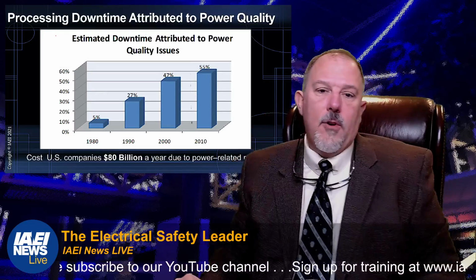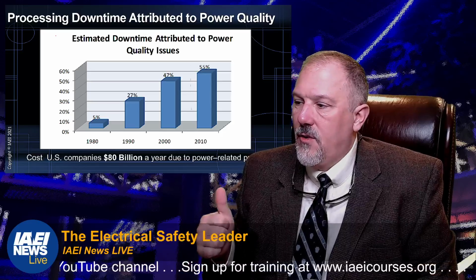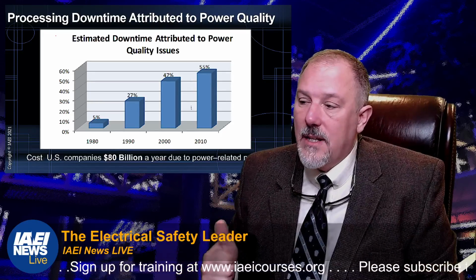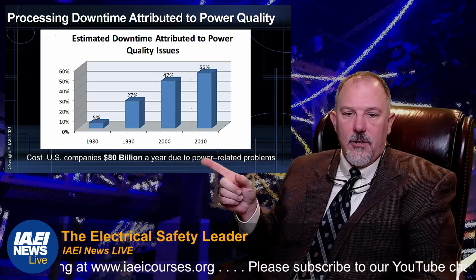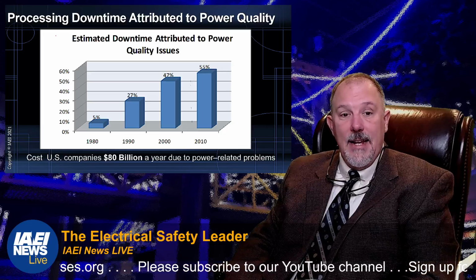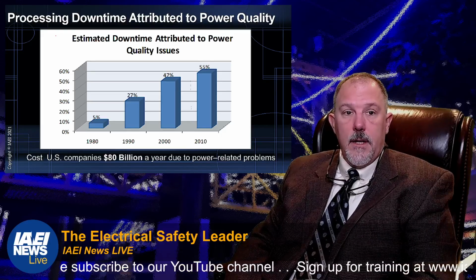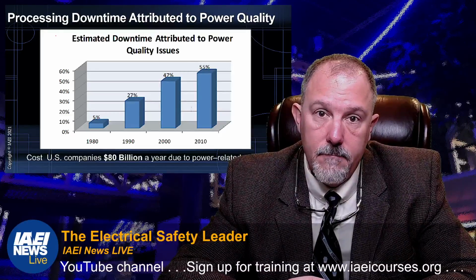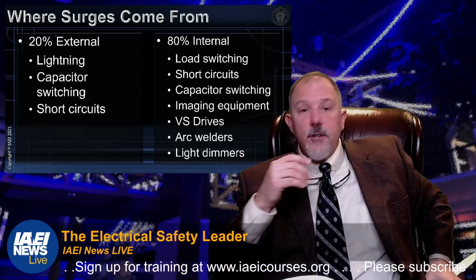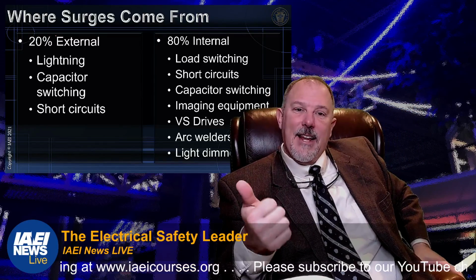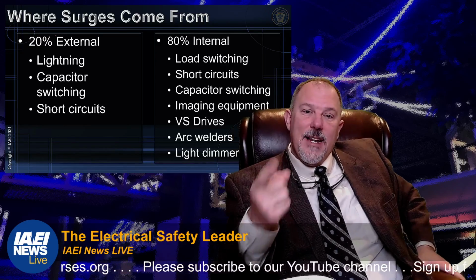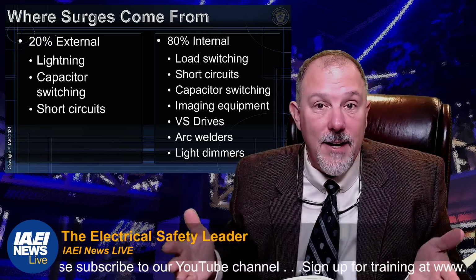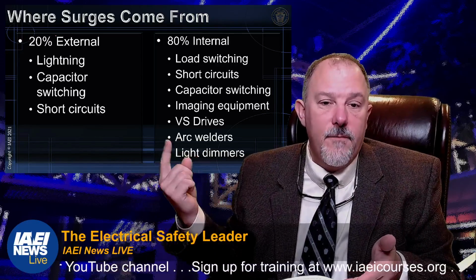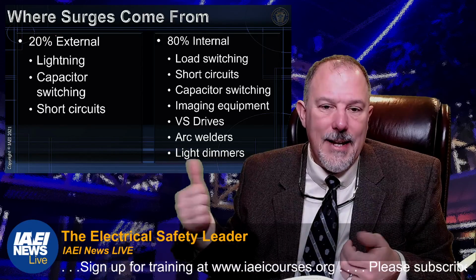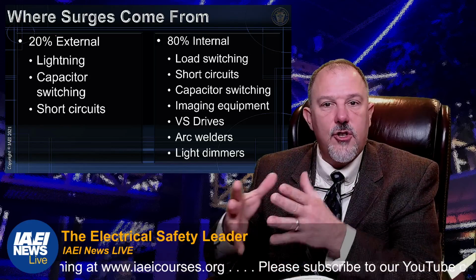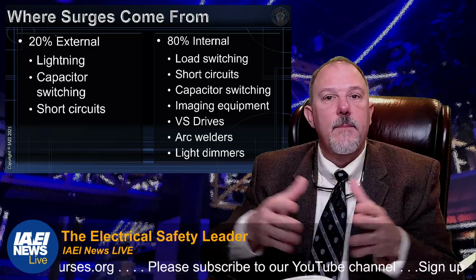Estimated downtime attributed to power quality issues, 55% in 2010, 47%. In the US, look at this number: $80 billion a year due to power-related problems. 80 billion. It's a lot of money. That's a lot of money that could be diverted into other areas, in my opinion. Where surge comes from: 20% external, lightning, capacitor switching, short circuit events. 80% internal, load switching, short circuits, but you never thought about that, right? Load switching, imaging equipment, variable frequency drives, arc welders, lighting dimmers. You can generate transient events from within the facility that impact other areas.